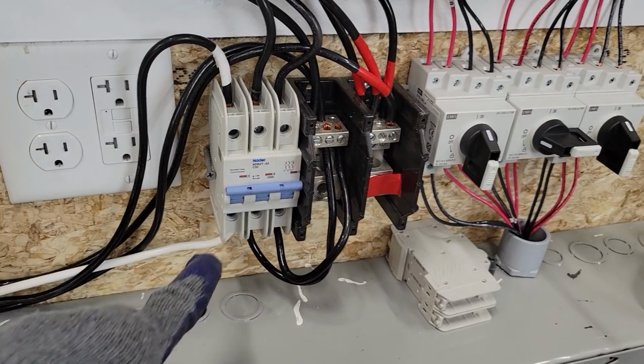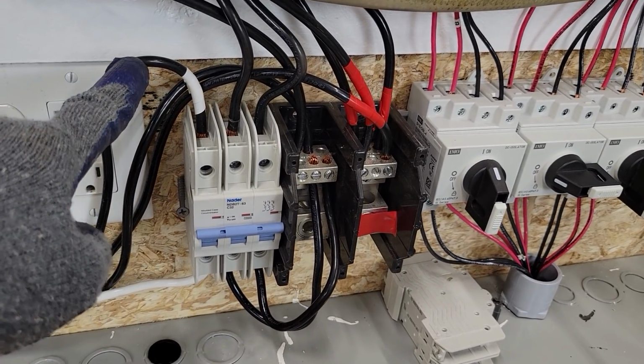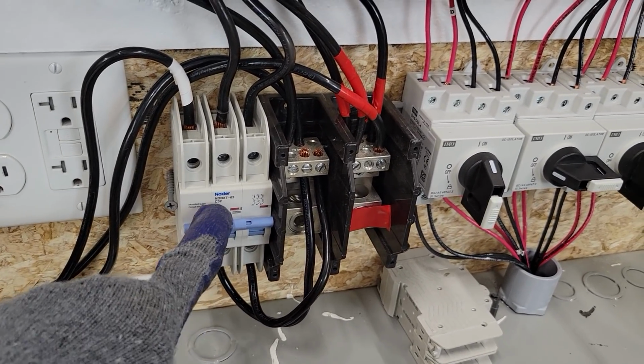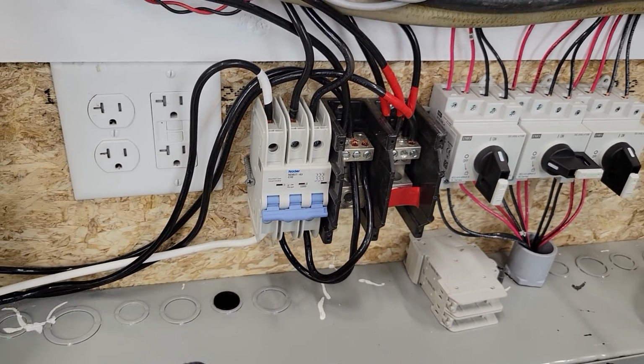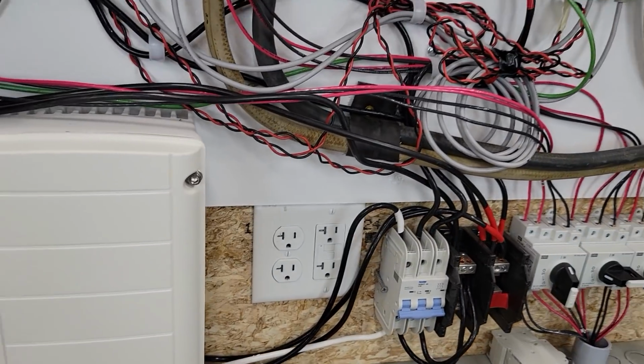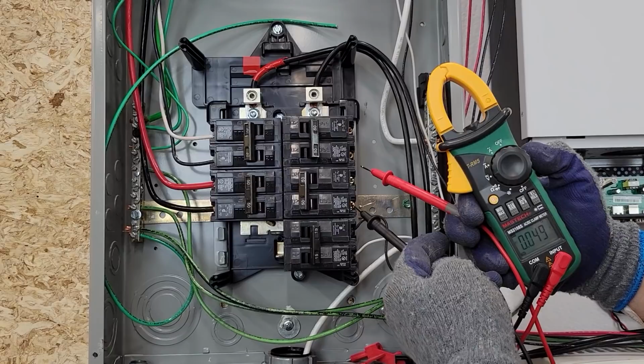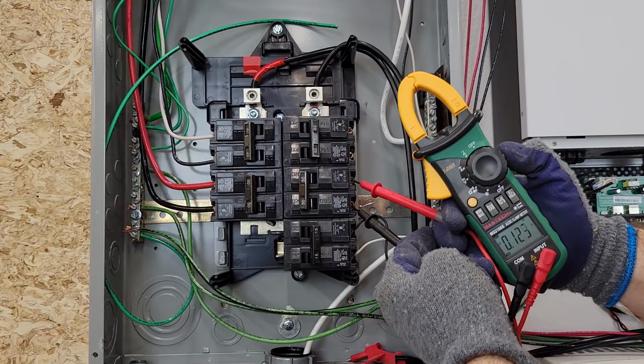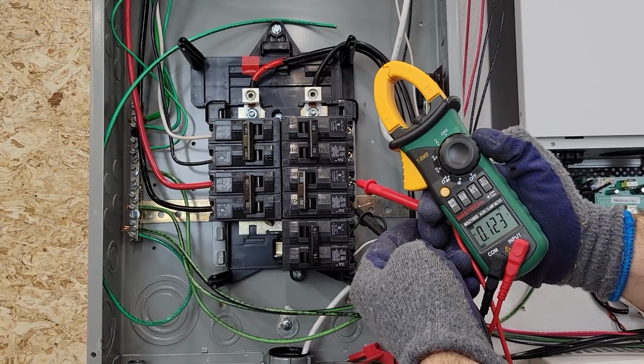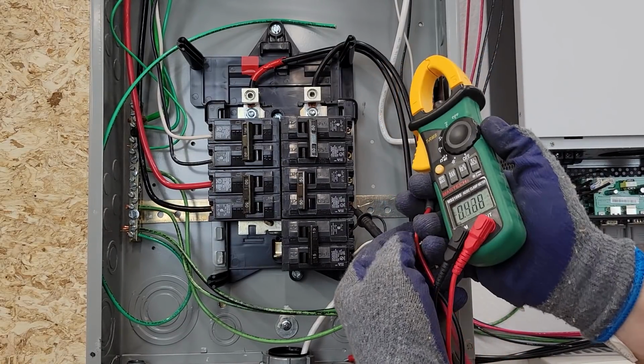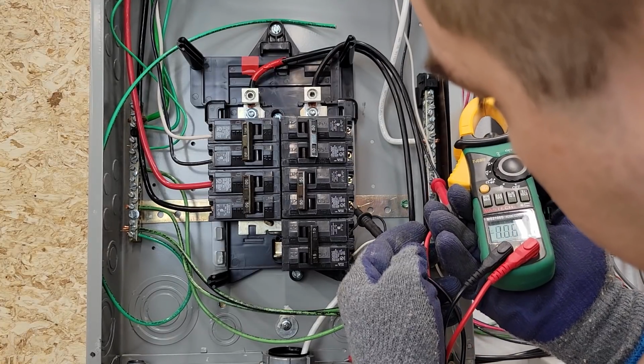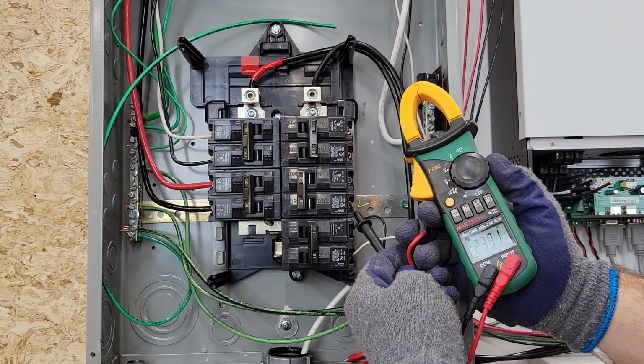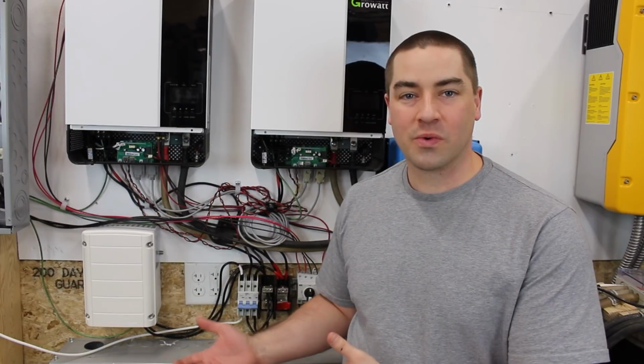Excellent. So if we overload this neutral wire, it'll flip that off, which will kill all the output. So now with that off, let's check the voltage again over here. And no voltage. And to the neutral, no voltage.